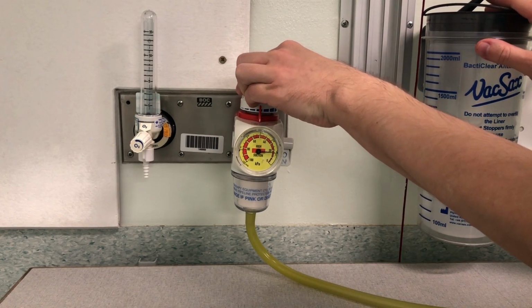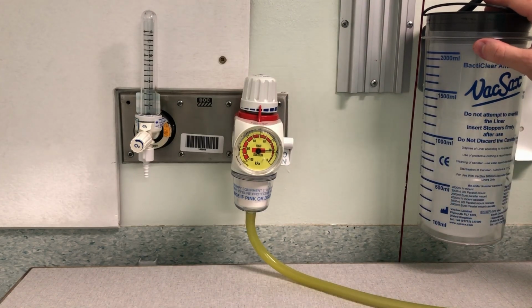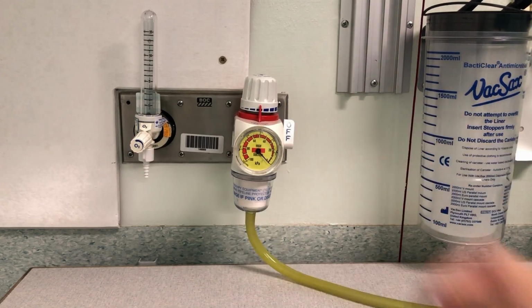So, things that might affect the safe operation and accuracy of the device. If the canister fills, it may affect the suction pressure reached. Suction pressure is required for oral, tracheal and thoracic. For oral suctioning, 20 kPa. For tracheal suctioning, you can also go up to 20 kPa. They don't ideally like you to go higher than that, as that can cause some damage. Thoracic suctioning is as prescribed or in the medical notes. It's usually measured in centimeters of H2O, and its max is usually about 4 kPa.